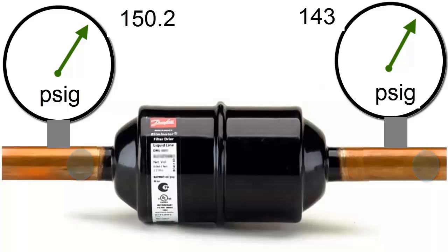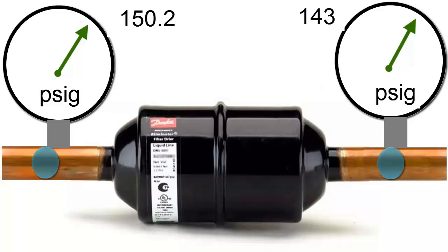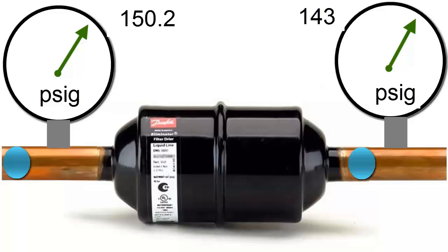Let's start by emphasizing that when a freezing, refrigeration, or air conditioning system has a clogged dryer filter, there is a noticeable drop in pressure in the refrigerant flow passing through that filter.